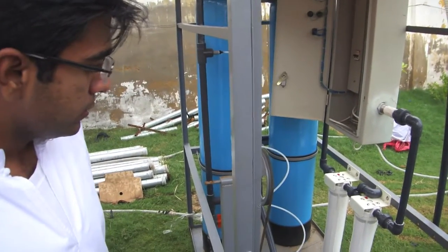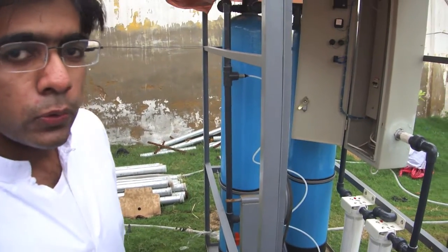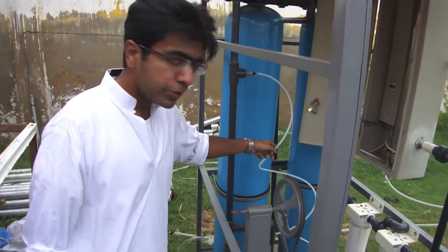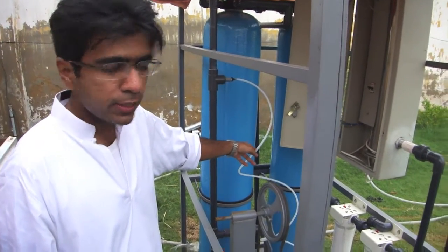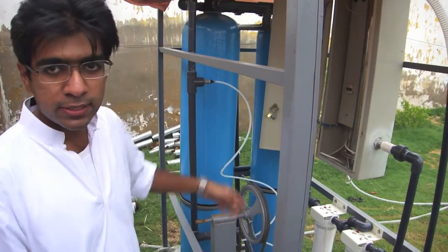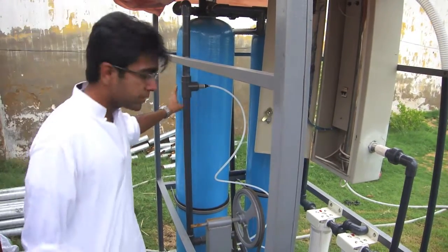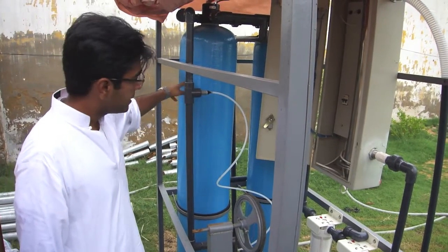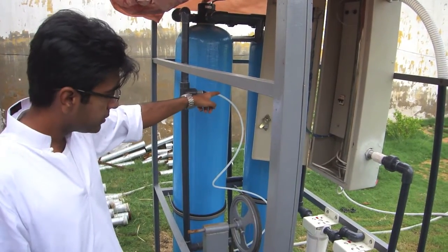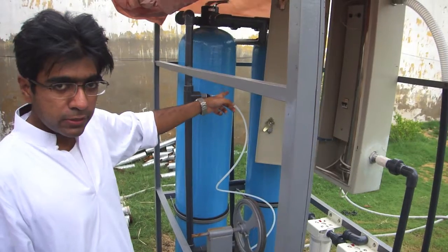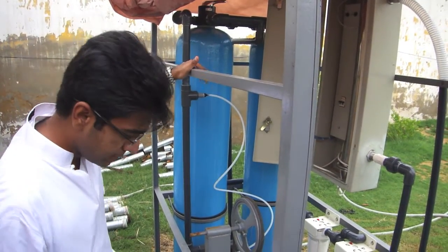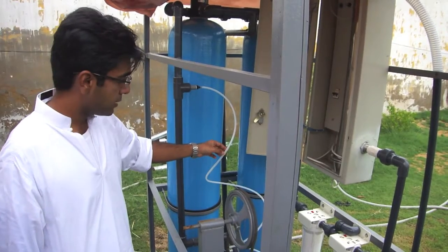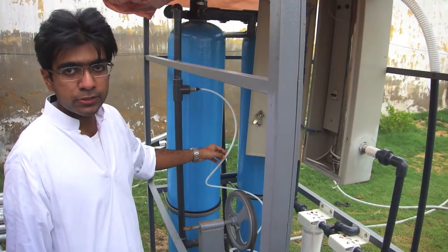If you just describe, I mean, if you give a typical example of what some water will look like, and what water contains. Number one, the chlorine would be an antimicrobial agent. It would kill all microorganisms, bacteria, parasites, etc. The sand filter is a particle filter. It will take out all the silt, any suspended particles, etc. and settle those down. The carbon filter can serve as a particle filter, but in this machine what we're using it for is to remove the chlorine from the water, as it is not advisable to give people water with chlorine in it to drink.